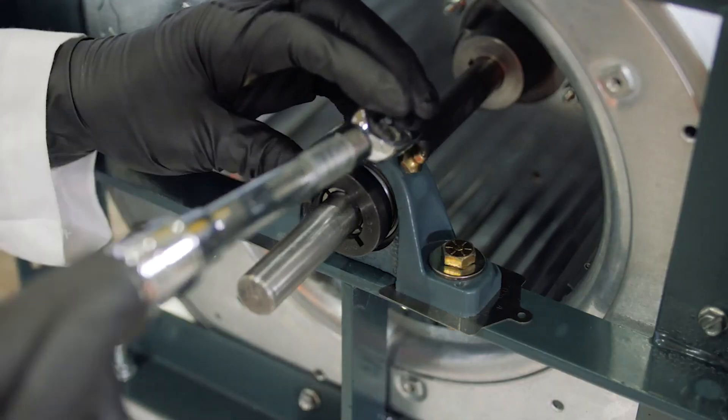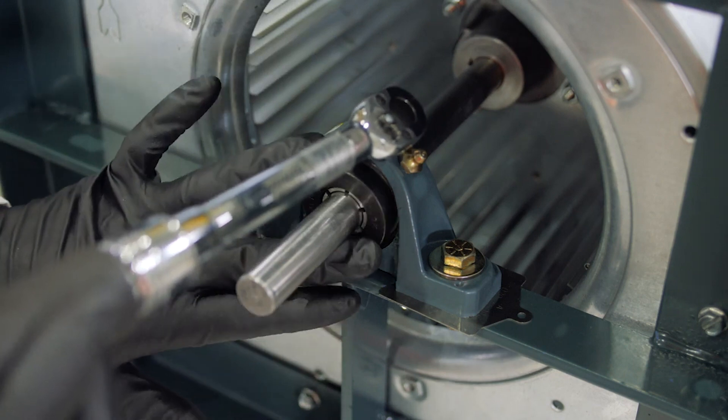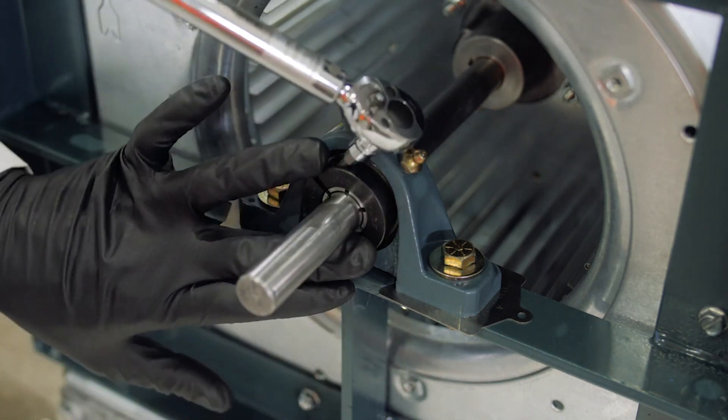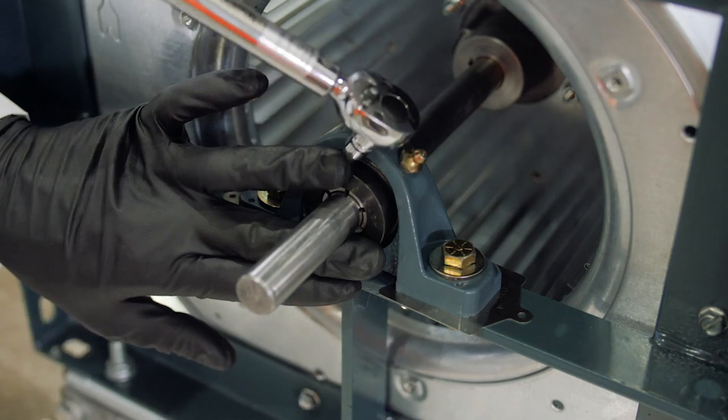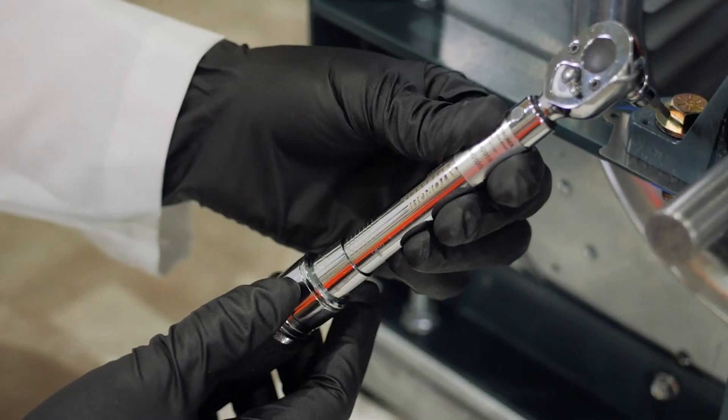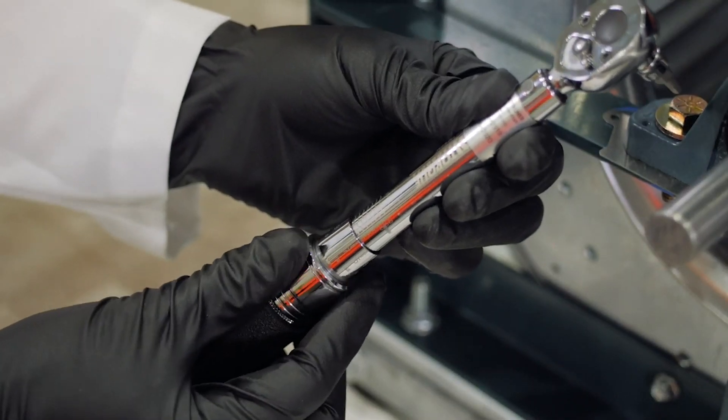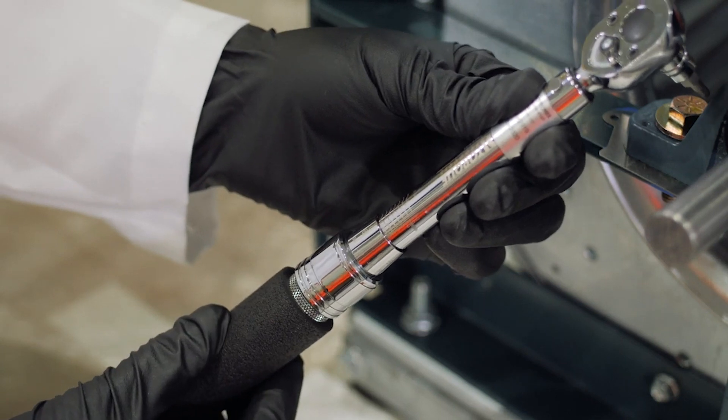Use your second hand to firmly hold the head of the torque wrench to ensure full engagement and perpendicularity. Tighten the cap screw until resistance is encountered. Next, using a torque wrench, tighten the cap screw to the torque value specified in the instruction manual.